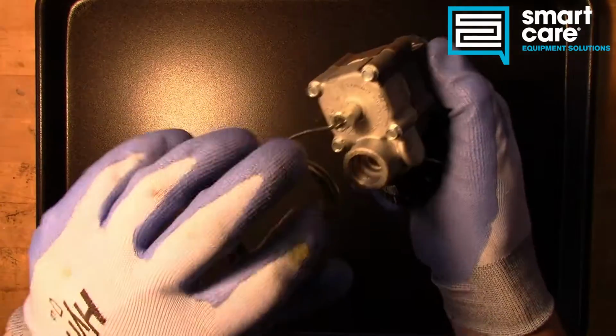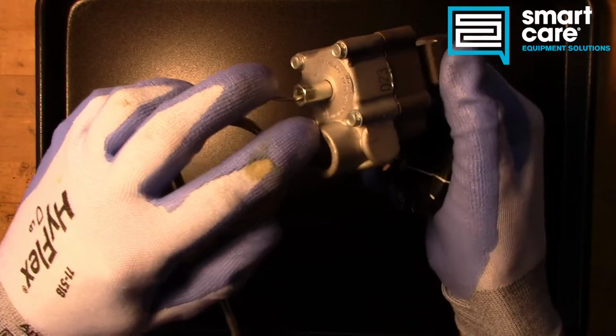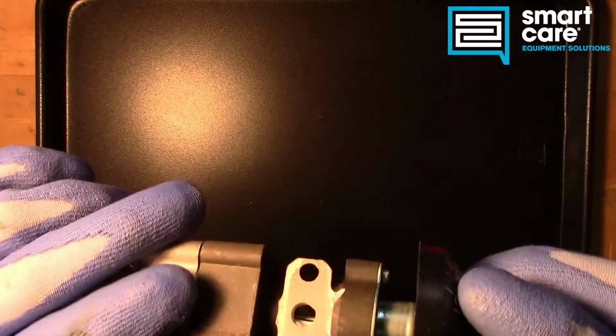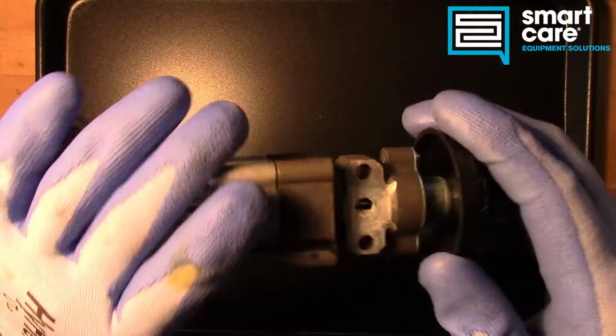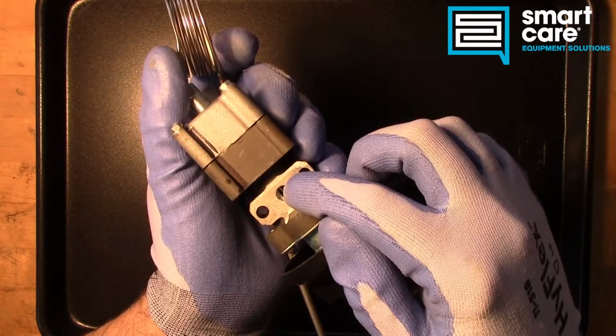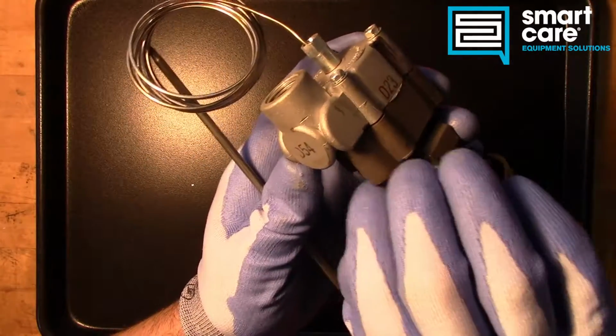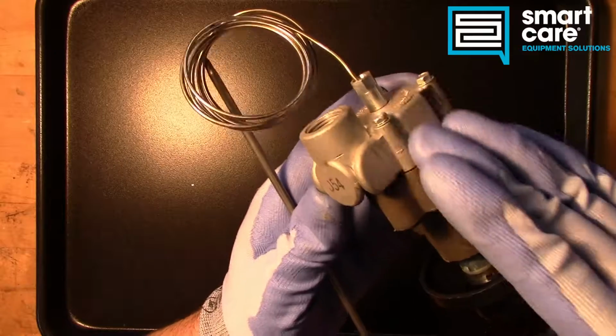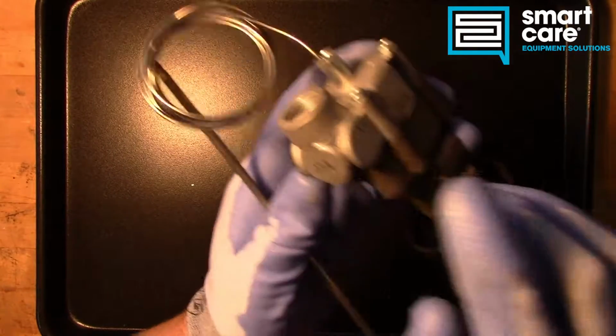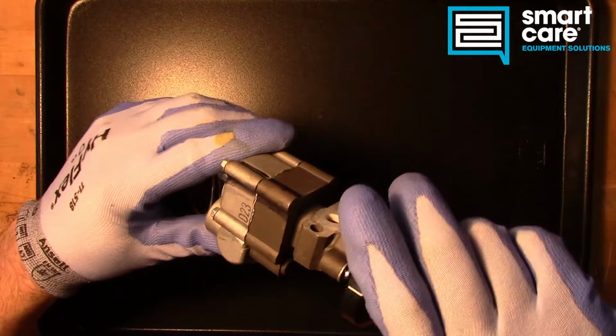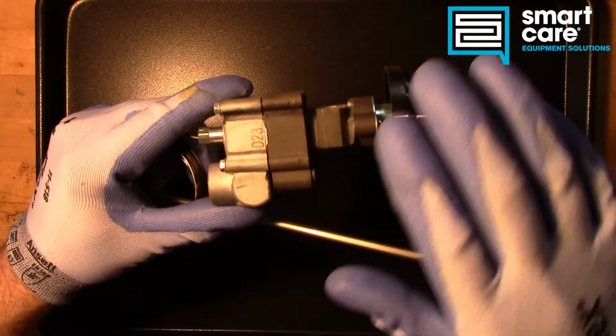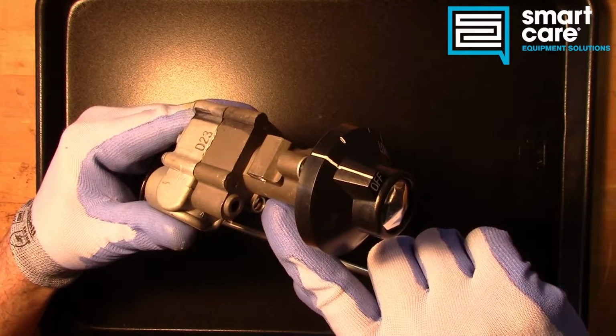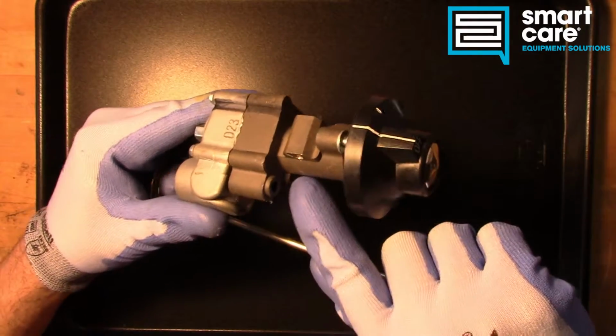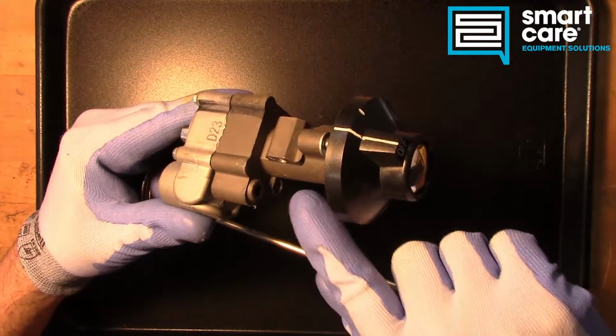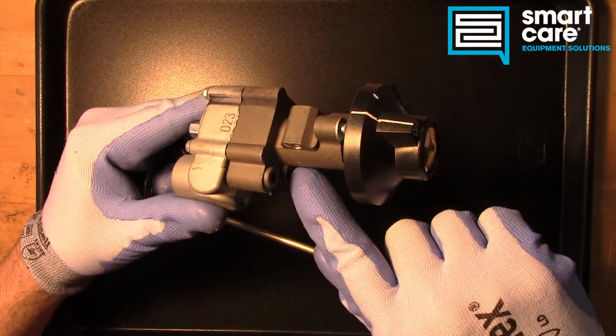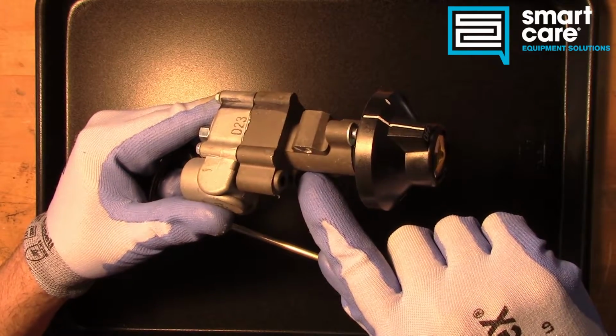The bypass allows some amount of gas to flow continuously out of the outlet regardless of the thermostat position, as long as it's turned past the off position. So anytime that gas is flowing into the opening, the bypass allows gas to flow through the body past the thermostatic control and out to the burner. We do that to keep the burner lit at a minimum flame. Now most thermostats ship with that screw all the way closed, and you as a technician have to make that adjustment when you install it. Never assume the bypass is set. Chances are it's not set for the piece of equipment you're installing it on.